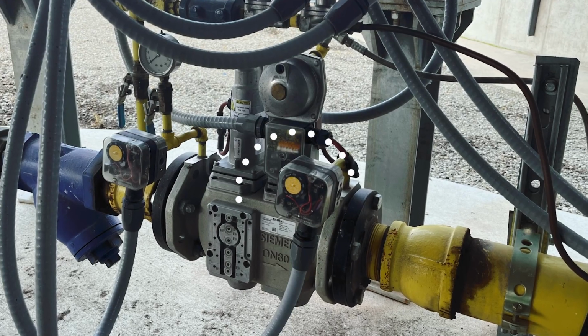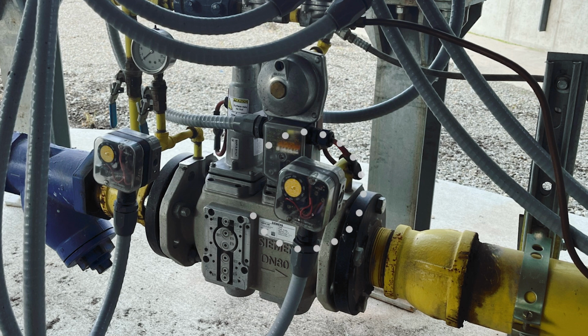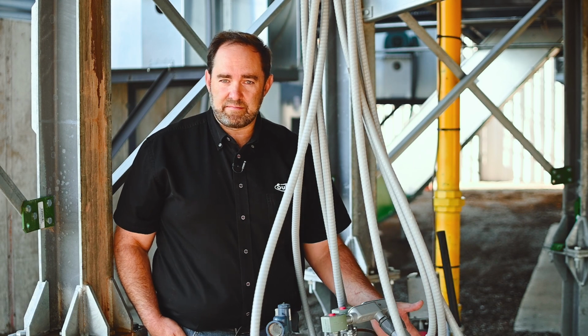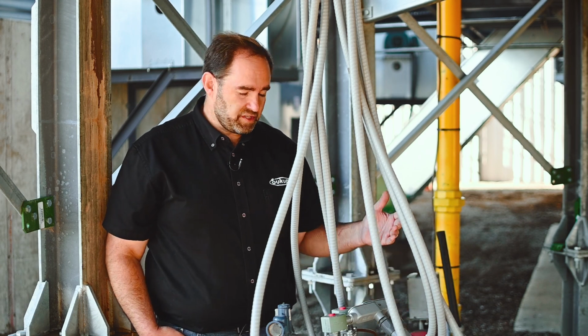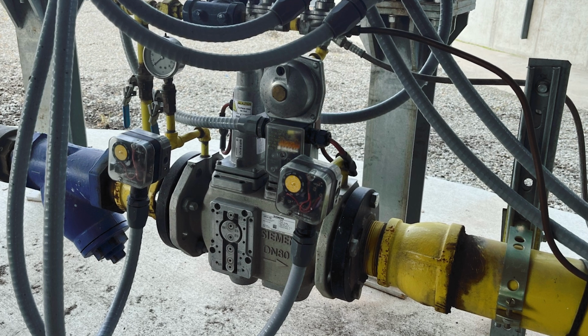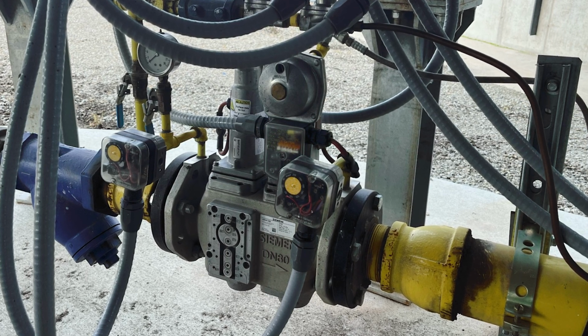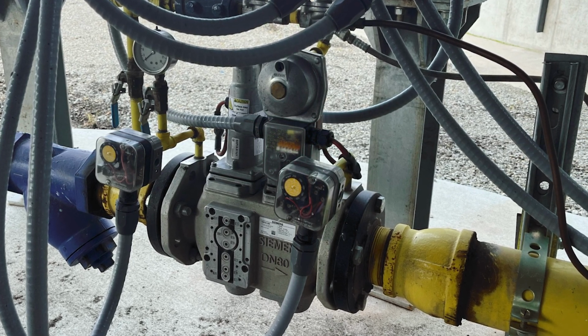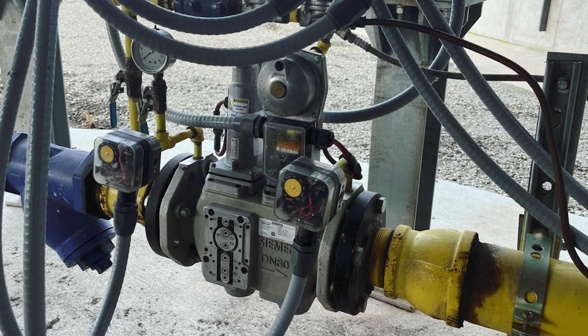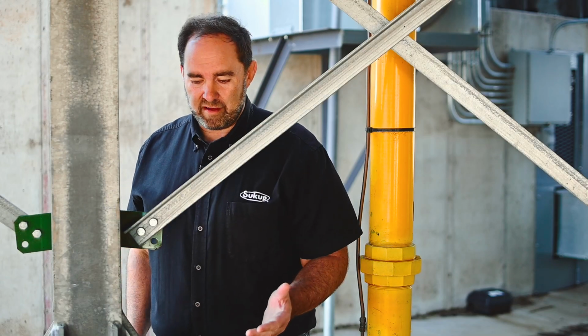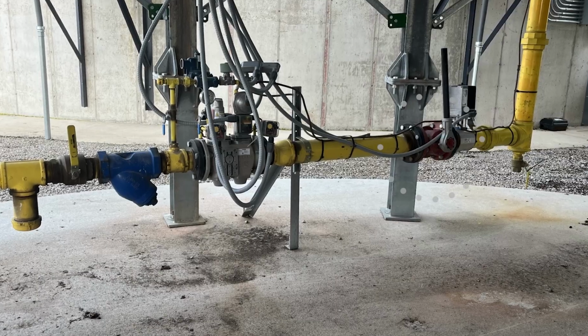Next is this high pressure gas switch. It's essentially the same thing as the low pressure gas switch, just set at a different number. That one will be set at 200 inches of water column. That would be on the discharge, or outgoing end, of the Siemens valve block. Okay, then after the Siemens solenoid valve block, we have a quarter turn shutoff valve, a red one here.